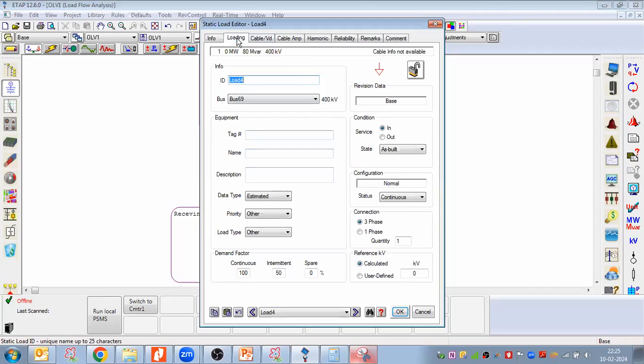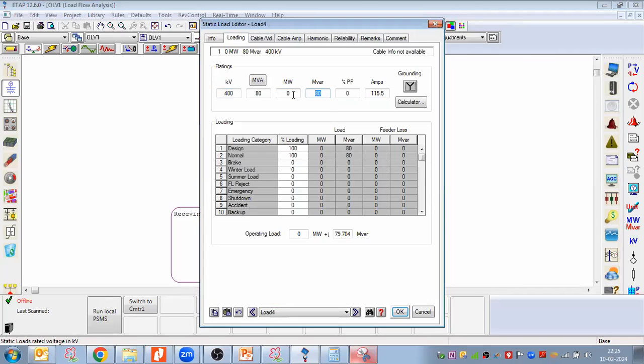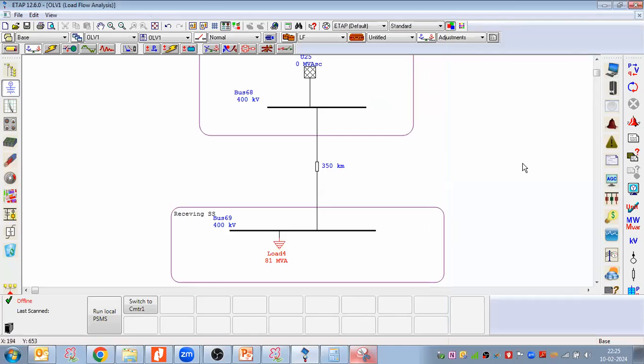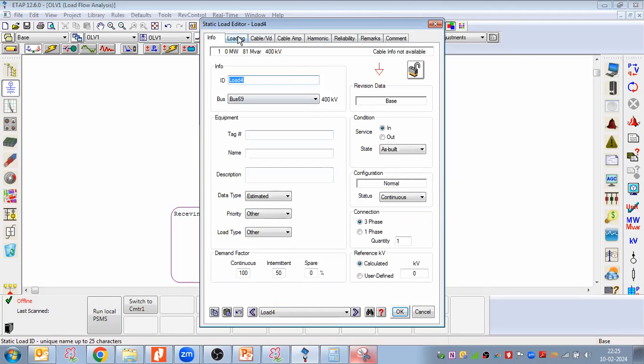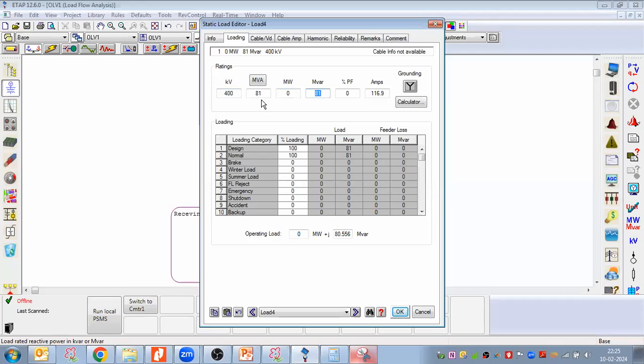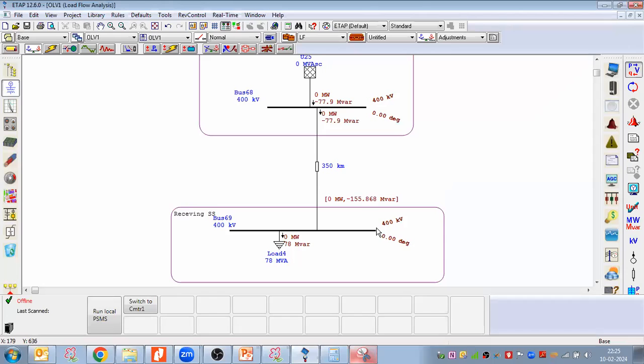I took the 80 MVAR. You can go and here you can play. Let us select 81 MVAR. Click on the OK. Then again perform the load flow: 398.9. So just like that we can simulate precisely 78 MVAR to reach till 400 kV. So if I took 78 MVAR precisely, the result is just 400 kV, which is required, right?